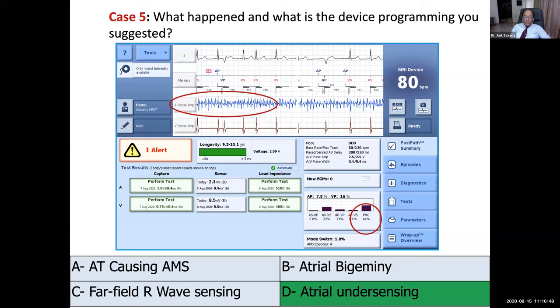This also causes one more problem: the PVC count is being shown as 44%. This may not be accurate, because as I told you earlier, if there is a V sense without any atrial activity, it will be counted as a PVC. Because the atrial channel is not showing any sensing, the pacemaker counts all these as PVCs, so the PVC count becomes artificially high. That's another problem.